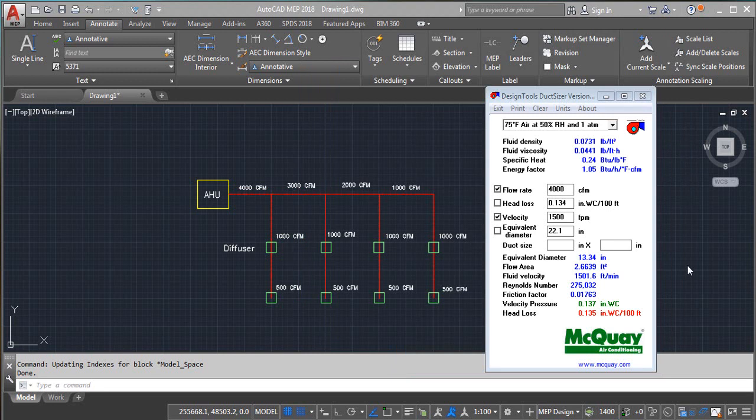The equivalent diameter for the main duct will be 22.1 inch in case it is a round duct, and in case it is a rectangular duct, the duct has two dimensions, height and width. You have to unify one dimension. I will unify the width, and you put the first dimension and the software will calculate the second one. If you enter the width, the duct sizer will calculate the height, and vice versa. I will choose the width to be 22 inches.